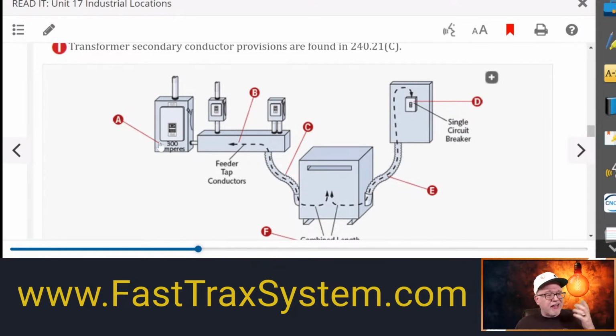Another interesting thing that I'll point out: say all this wasn't here. Let's say we had a disconnect right here, and it has the overcurrent protection in there, let's say 300 amps. Could I come out on dual lugs and one come out from here and hit a transformer over here, and then this one come out and hit some other load? Yes. Could I apply the feeder tap rules here? Yes, because the feeder taps don't always have to be tapped physically to a conductor. They can be on the load side of the overcurrent device, and that would still be considered a feeder tap.